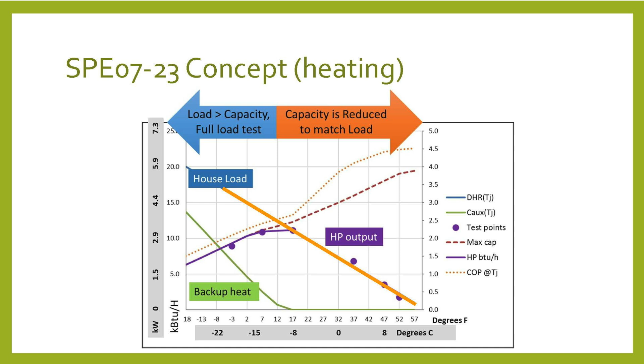And so how this works in the laboratory, typically on the left is one psychrometric chamber. There's mechanical equipment in the duct that runs outside the room, that is there to maintain particular temperature and humidity conditions in the chamber. And a similar thing, the outdoor room is on the right, and that also has reconditioning equipment that manages the conditions in the chamber. And in a typical fixed speed test, this is what you get. You get two psychrometric chambers, and the indoor conditions are just fixed, and the outdoor conditions are fixed, and they run it in the test mode, and they see what happens with the equipment, which is usually not a surprise, because they know how it's going to run.